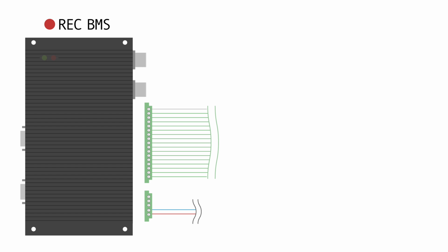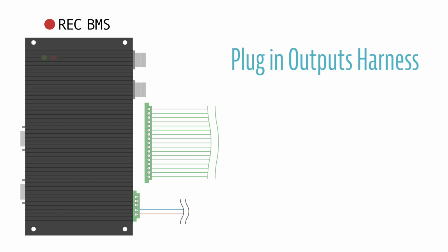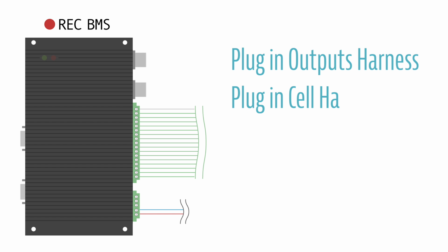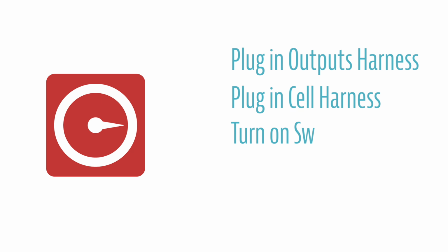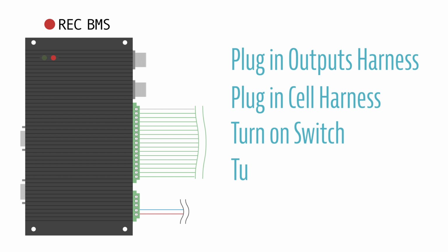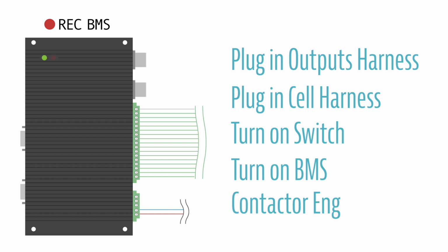Number 1, plug in the outputs wire harness on the BMS. Number 2, plug in the cell wire harness on the BMS. Number 3, turn on your battery disconnect switch. Number 4, turn on the BMS—you'll see a red light. At this point, the BMS is going to run a bunch of checks. After 7 seconds, if all is well, you will hear a clunk of your contactor and the light will turn green, and that means the BMS says everything's good.